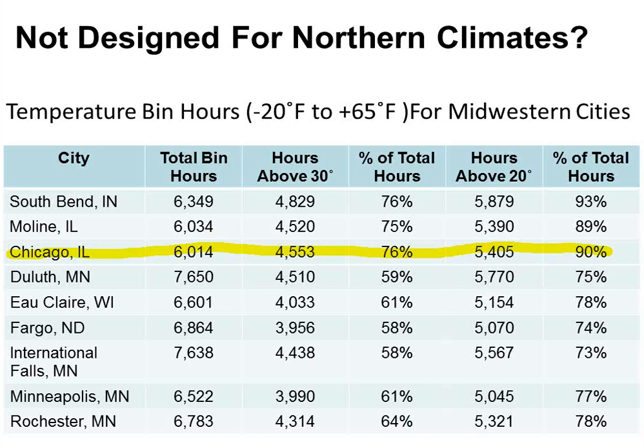So with these units, we're not controlling discharge air temperature, Mike. We're controlling the comfort level of the zone, and it's generally designed for a residential system. So we're specifically thinking mostly about floor-based heating diffusion, where that 90-degree rule doesn't come into play. So yeah, oftentimes you'd be seeing 100-degree discharge on these units, whereas you might want to stay under 90.